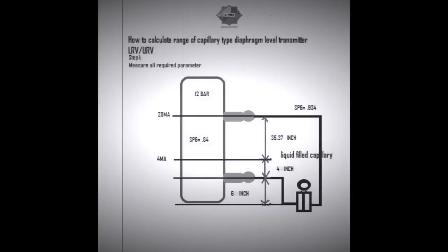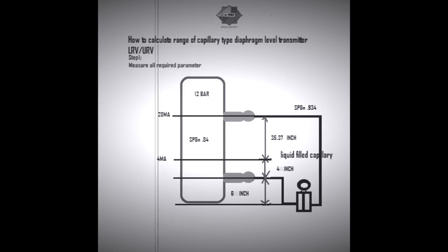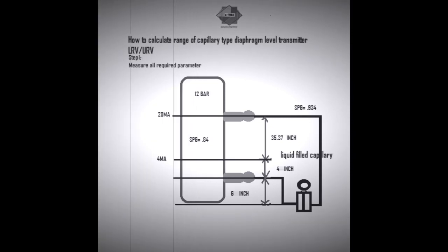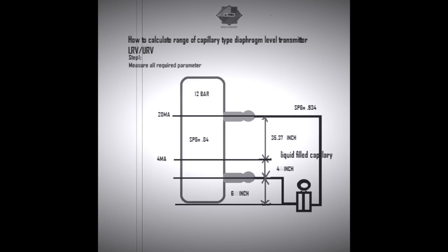Good morning engineers. Today we are going to study how to calculate a range of capillary type diaphragm level transmitter in the field of level measurement. For that, first we need to measure all the parameters: what is the zero percentage level, what is the 100 percentage level, what is the process gas specific gravity, and what is the capillary liquid fill specific gravity. Then it is easy to find LRV as well as URV.